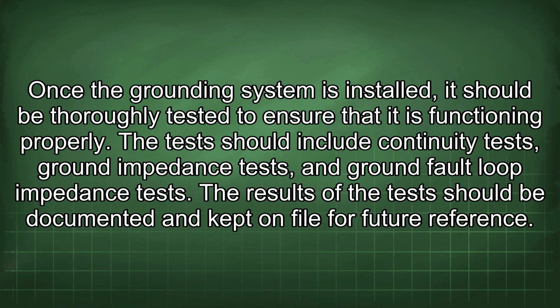Once the grounding system is installed, it should be thoroughly tested to ensure that it is functioning properly. The test should include continuity tests, ground impedance tests, and ground fault loop impedance tests. The results of the test should be documented and kept on file for future reference.